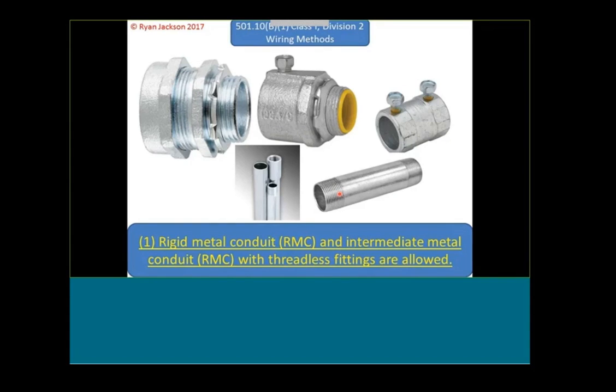We made a change in Article 501 that says in Class 1 Division 2 locations, we can now use threadless fittings. Where was this when I was alive? I did a bunch of threaded conduit work. When I was learning tools, I did a bunch of threaded work. And I'm here to tell you, if you've never really run threaded pipe, and I mean really ran it, not just put in a stick, I mean did a whole job in threaded pipe, let me tell you, that is a whole different ball game. It's barely even the same sport as running EMT. You might be a wizard at running EMT conduit, bend it, do whatever you want with it. When it comes to running threaded pipe with threaded fittings, that's a whole different skill set, and it's so much more labor intensive.